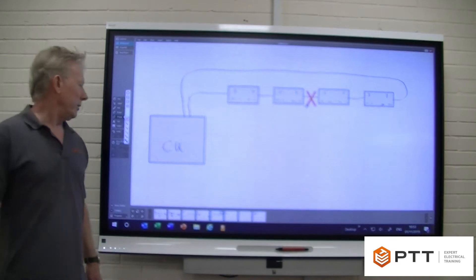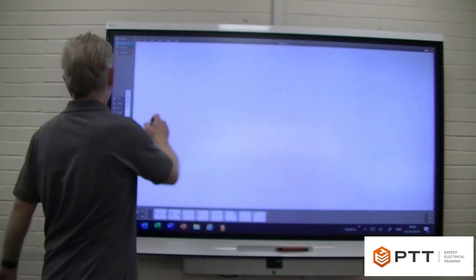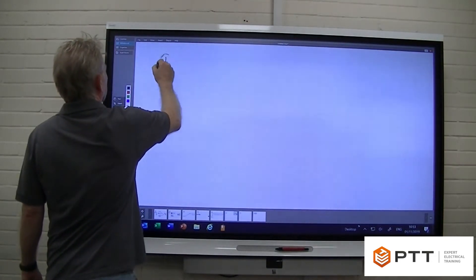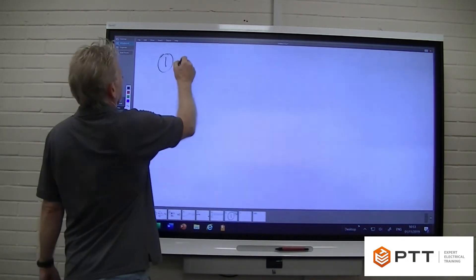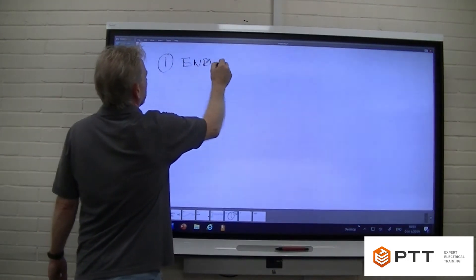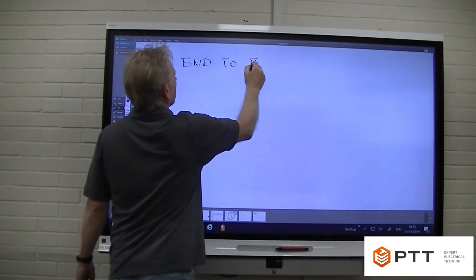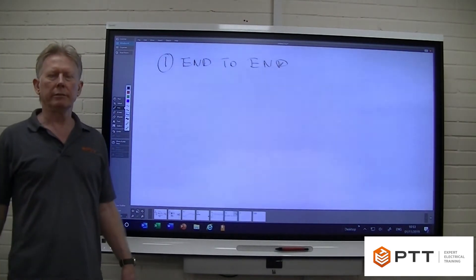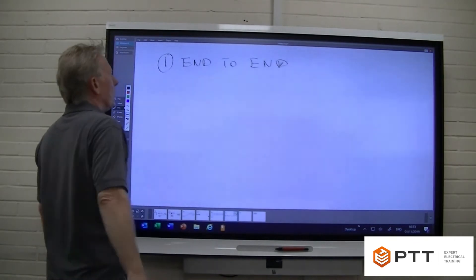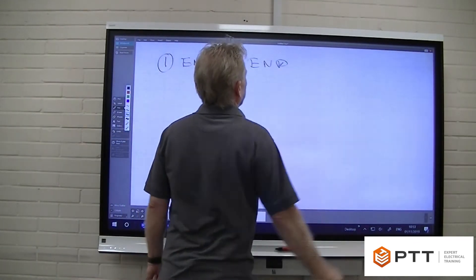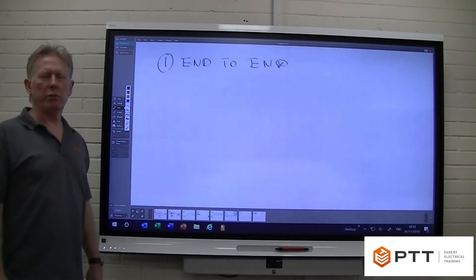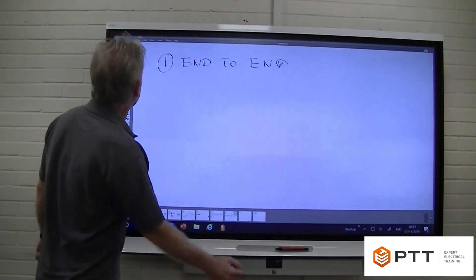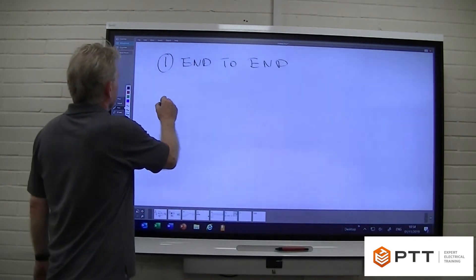With the ring, basically there are three tests. Test number one is actually what we call end-to-end resistance. The whole point of that test is we actually want to prove it is actually a ring. Once we've got the results from this and once it passes that test, it allows us to do some calculations. We're going to be making some cross connections later to actually check that the ring is working satisfactorily.